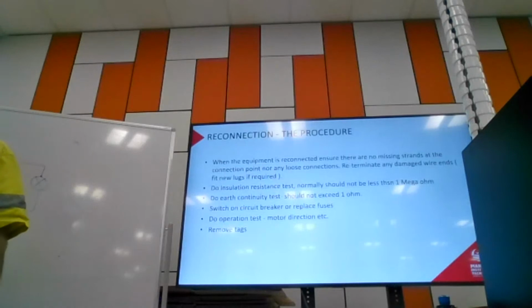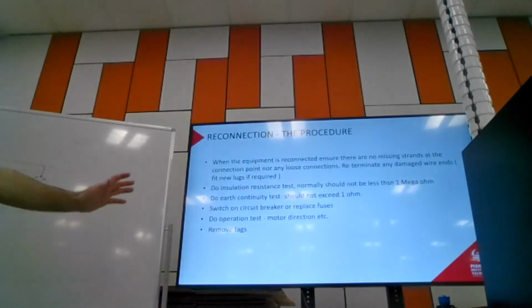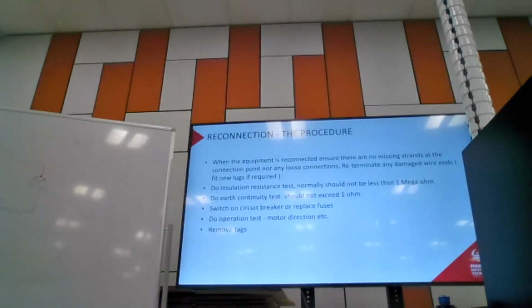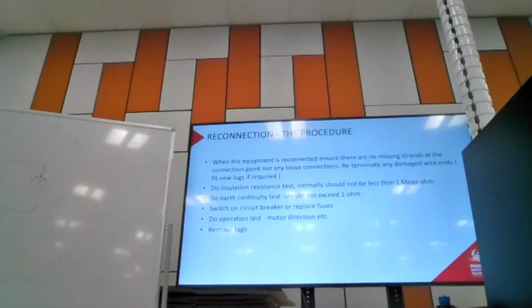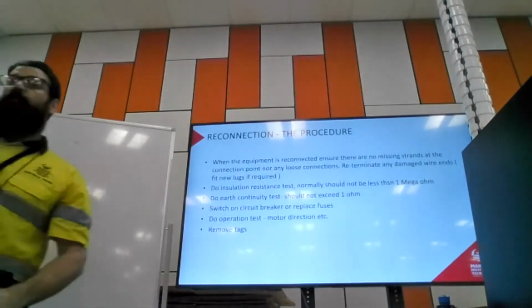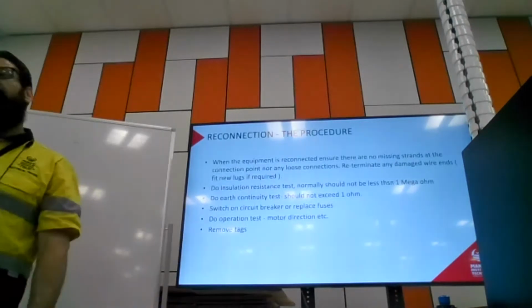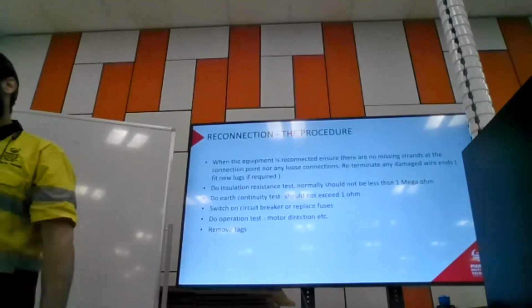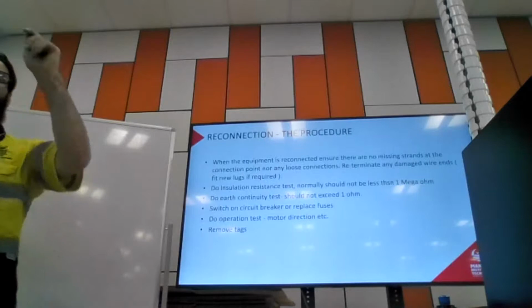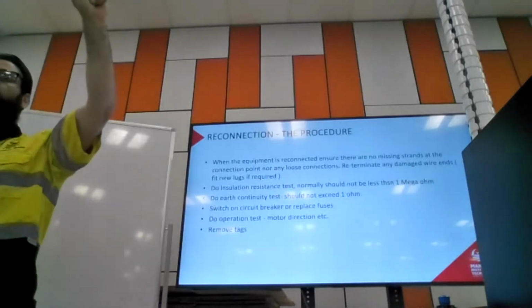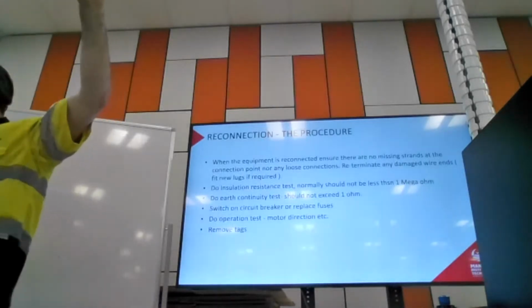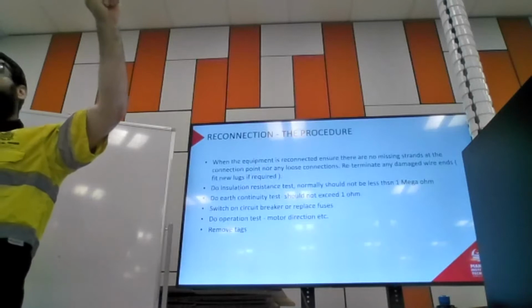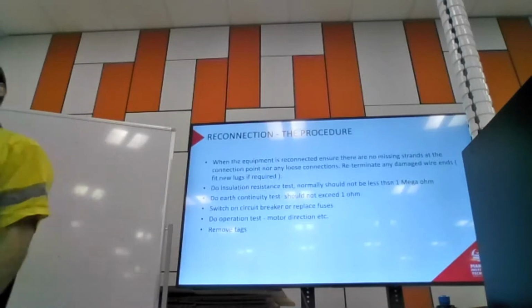No idea. And an appliance. In an appliance, 1 ohm is a satisfactory earth continuity result. For our main earth, so from our earth busbar in the switchboard to our earth stake, that's 0.5 ohms. For our earth continuity conductors, so from our earth busbar in the switchboard out to each individual earth wire on every sub-circuit, then it depends.